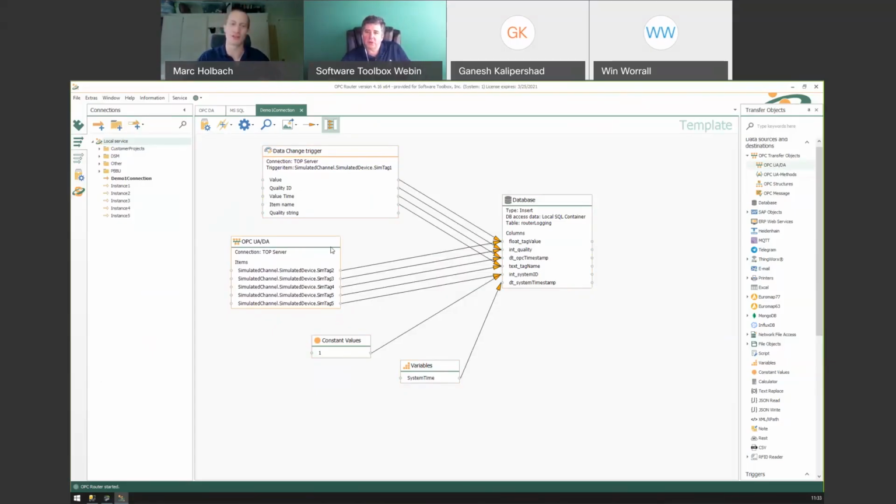I think there's a big difference. For example, this individual has been sharing some application details, and I don't want to go too far in the weeds because we want to do the second part of the class and then circle back. But it sounds like he was doing something with 150 tags coming off an OPC server being logged at a 1 second interval. And I think based on some of the stuff you've done, that's a pretty light application for this, isn't it? Yeah, 150 tags at a 1 second update, I see no reason that wouldn't work.